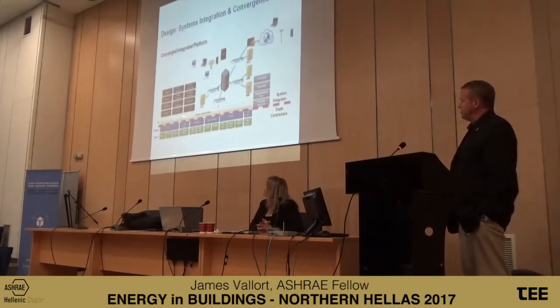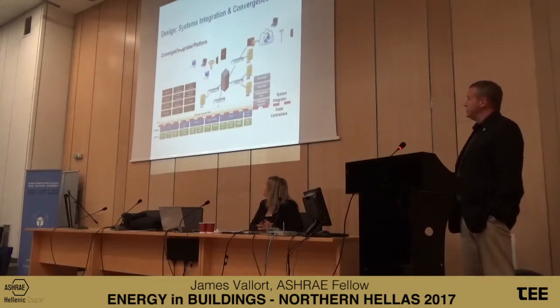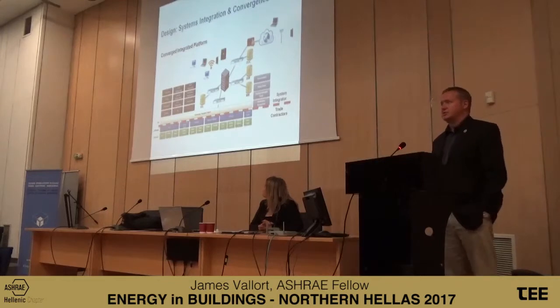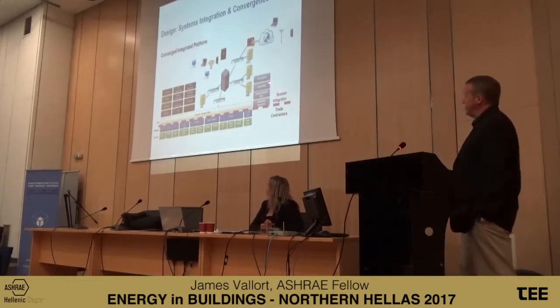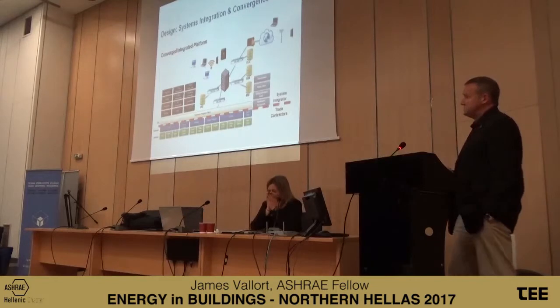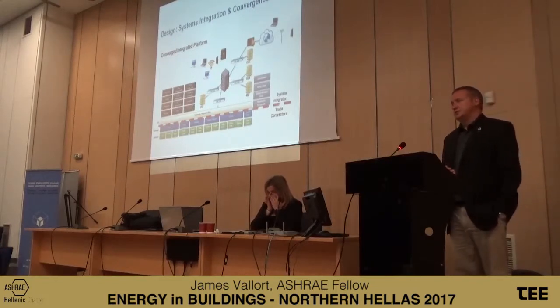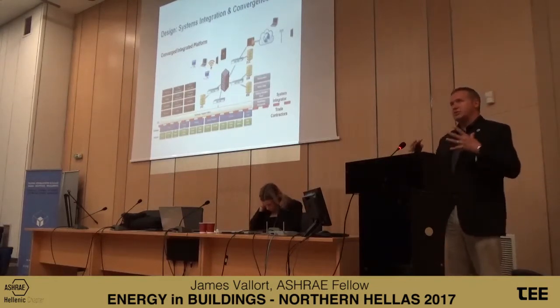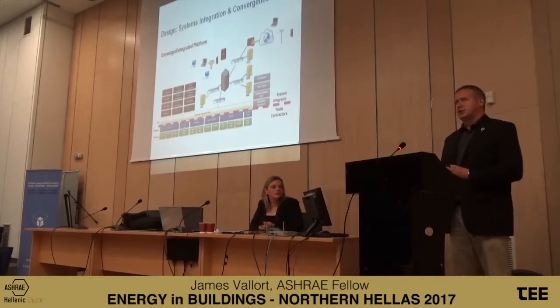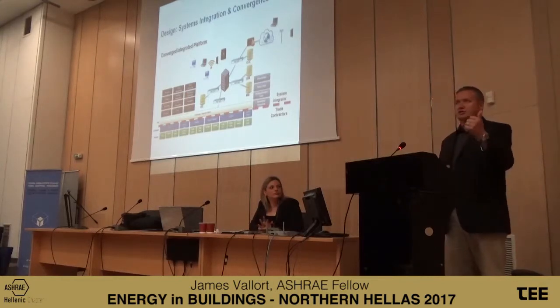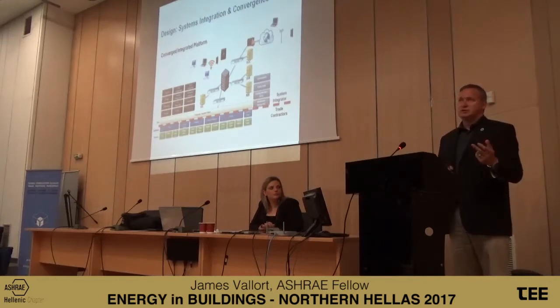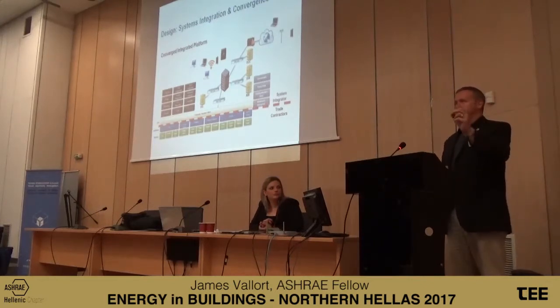With this middleware, we end up with a central platform for communication, a single point of connection to the outside world to monitor. One key thing: if you have a BIM model, like Revit, it makes this so much easier. For new construction, putting together this intelligent platform is much easier than for an existing building. If you pulled the as-built drawings for this building and compared the mechanical, electrical, and plumbing sets, I guarantee half the rooms have different numbers, C102, C space 102, C-102.